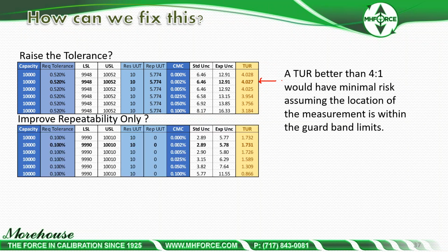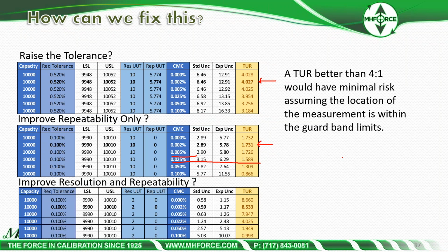Other thing we can improve is if we just improved repeatability. We're not going to get to 4-to-1 TUR if we just improve repeatability, but we could take more measurements. And if we take more measurements and improve the repeatability here, we can get to a 1.731. This is assuming dead weight. It's very hard to calibrate these scales in dead weight. So that's another thing that we're looking at. More than likely, someone's down here using a secondary standard at this 0.025, and they're having a TUR of 1.58 to 1. This is what we did in a study.